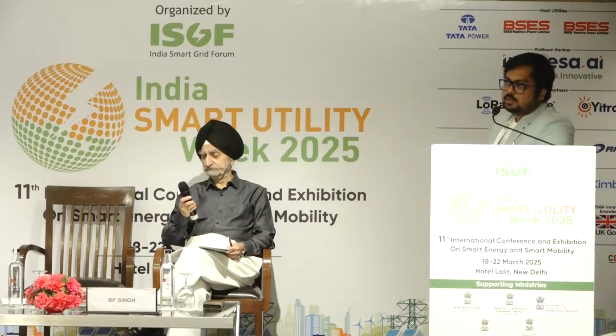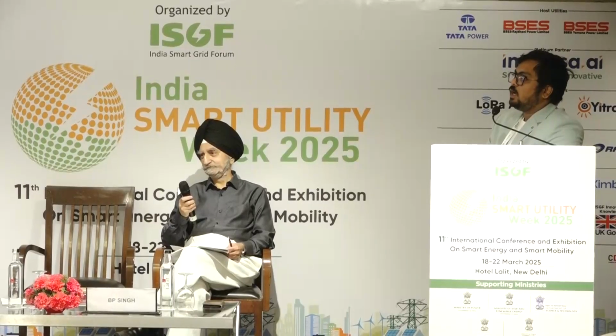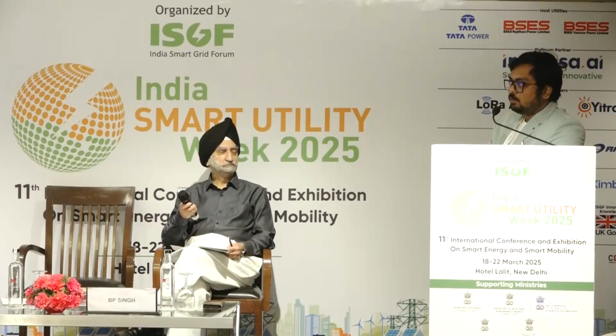Sir, actually it is a very good question. We already discussed the studies for microgrid in grid-connected mode, but mainly when grid is not present, the magnitude of the current is very low. In grid-connected mode, the fault current will be provided from the grid, so the conventional system is more than sufficient.